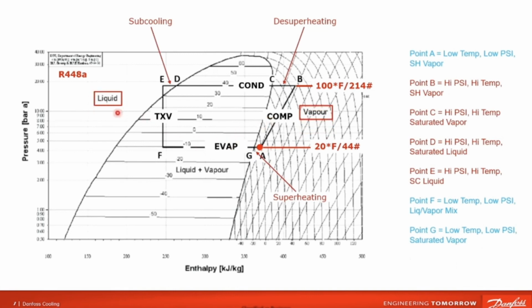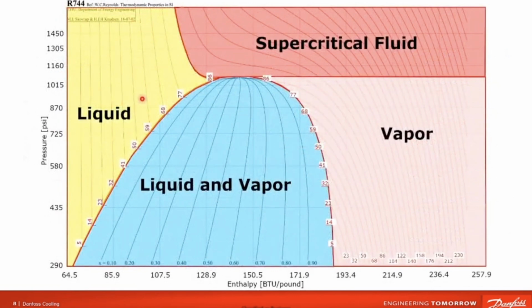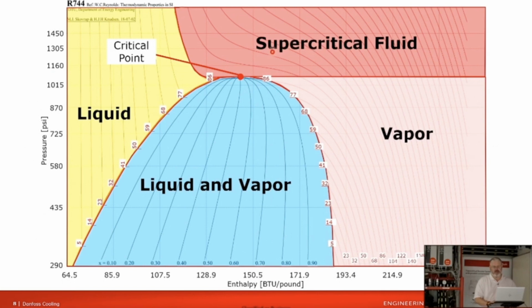And we want to remember liquid and vapor states. That's a really key ingredient to understanding CO₂, because with CO₂, we have a new thing. We have a critical point that we will operate above, which puts the refrigerant in a condition called supercritical fluid. The density of the refrigerant at that point is so dense that you can't really distinguish a vapor particle from a liquid particle. And basically you can't flash it off in an evaporator. So our system has to have something to bring us back into the dome, because that's where we get work accomplished.